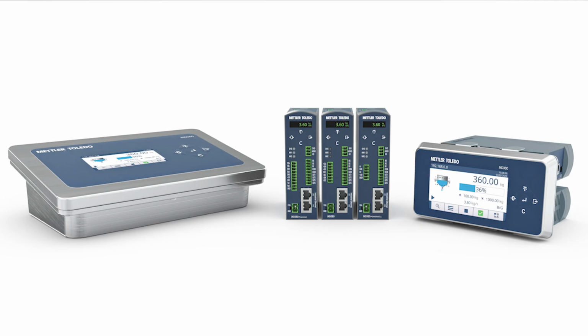With MultiACM, not only is the automation system flagged immediately that there's a problem, it'll actually tell you which load cell is the problem. So when the maintenance tech goes out to start troubleshooting, he doesn't need to spend extra time identifying where the issue is—he can get right to work.